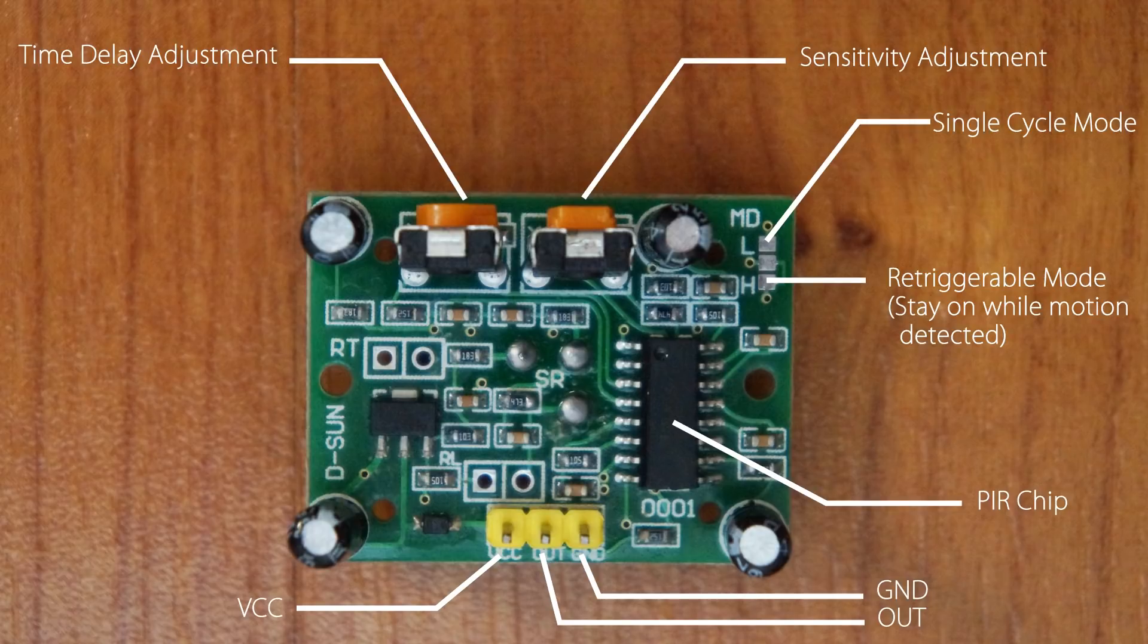Next we have the time delay adjustment. This knob allows you to adjust the time delay between five seconds up to five minutes. Turning the knob counterclockwise decreases the time delay while clockwise increases the time delay up to five minutes.